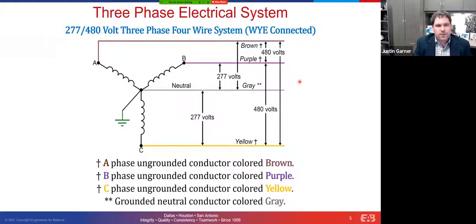But the vast majority of the time in most commercial applications, we're going to see this application because we use this 277 volt component, or the single phase component, of this power system for various things like lighting and smaller electrical loads on the HVAC side, such as electric duct heaters, maybe fan-powered boxes, terminal units, and things of that nature that still may draw too much amperage to put on a 208/120 system, which we'll talk about next, but obviously don't need full three-phase power.